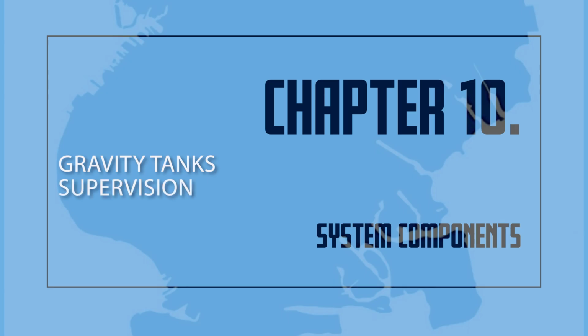Gravity tank supervision. The gravity tank shall be constantly monitored to ensure that the tank and its parts are working. Electrical supervision devices monitor the water temperature and the water level in the gravity tank. These devices send signals to an approved central station company about the water level and water temperature. The central station company notifies the certificate of fitness holder when a problem with the gravity tank is detected. The certificate of fitness holder shall correct the problem as soon as possible. The supervisory devices are sometimes called high and low alarms, since they also send audible signals to alert the certificate of fitness holder or central station when there is a problem.